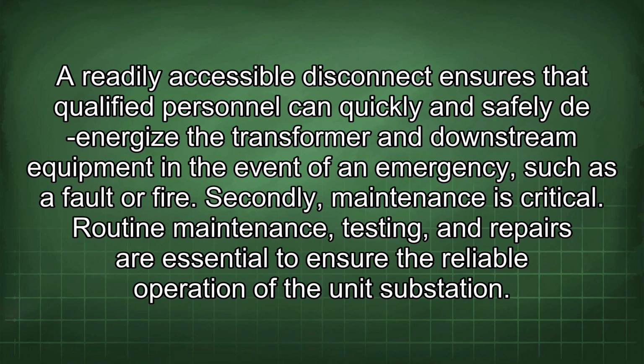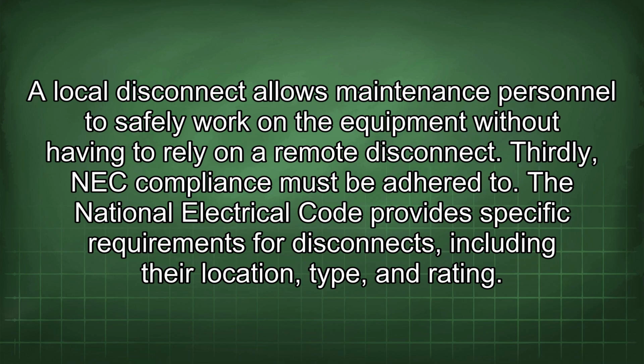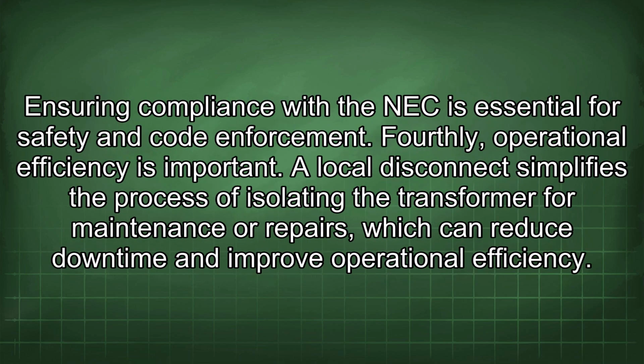Secondly, maintenance is critical. Routine maintenance, testing, and repairs are essential to ensure the reliable operation of the unit substation. A local disconnect allows maintenance personnel to safely work on the equipment without having to rely on a remote disconnect. Thirdly, NEC compliance must be adhered to. The National Electrical Code provides specific requirements for disconnects, including the location, type, and rating. Ensuring compliance with the NEC is essential for safety and code enforcement.